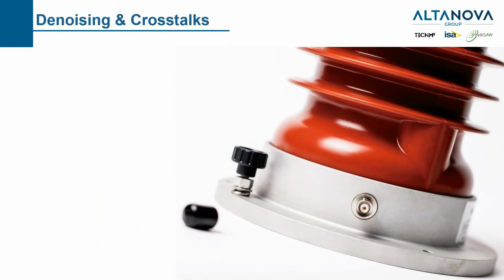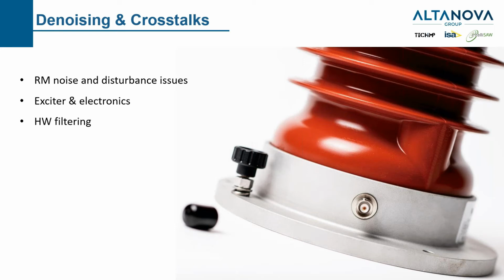To carry out a proper data analysis, the first step is to identify and remove the noise occurring in the generator measurement and the eventual phase-to-phase crosstalks. We will see what are the classic rotating machine noise and disturbance issues, in particular the exciter and electronic system noise. Then we will see a solution for such noise like hardware filtering. And later on, we will introduce the Techimp patent about time frequency map filtering, which is a more customized solution.